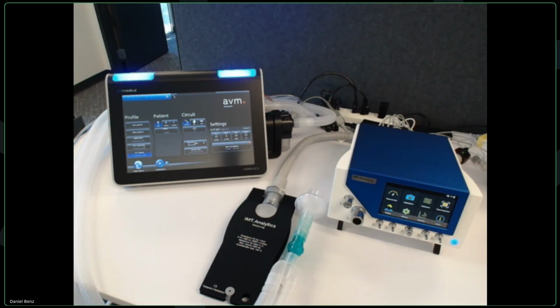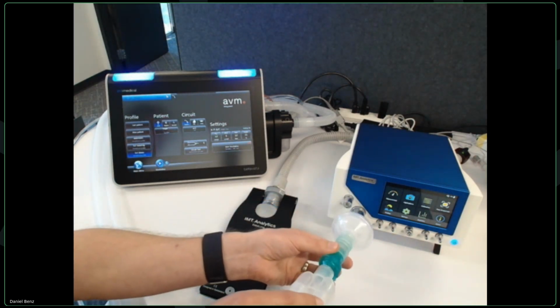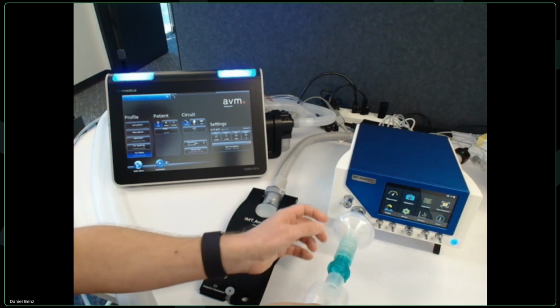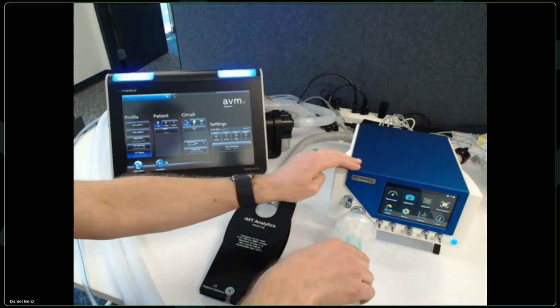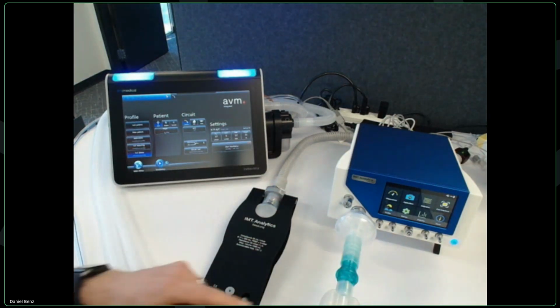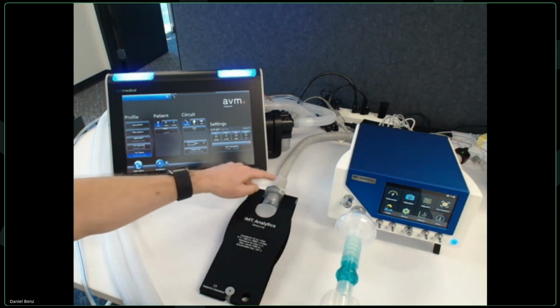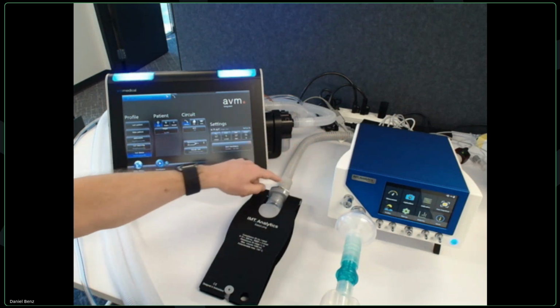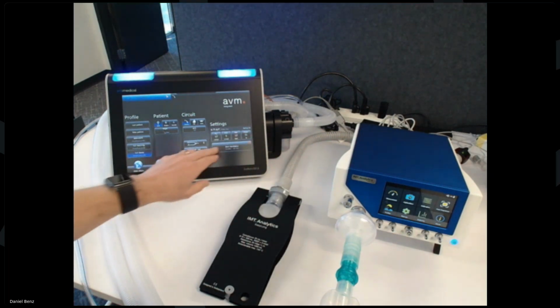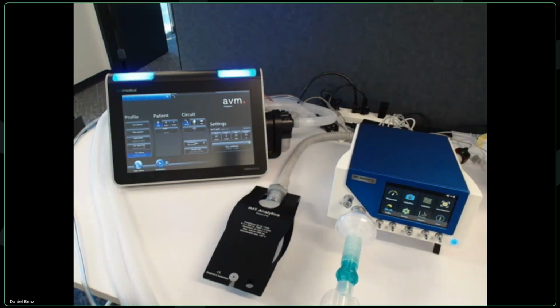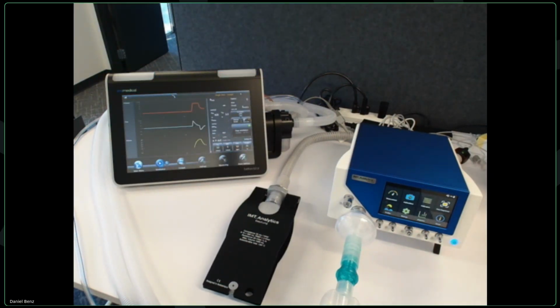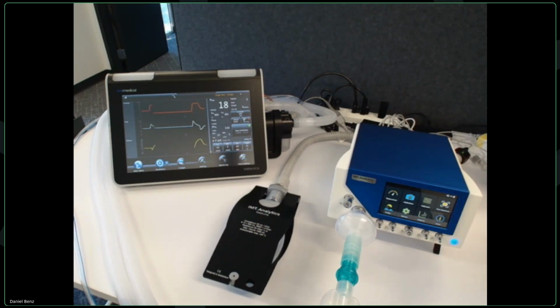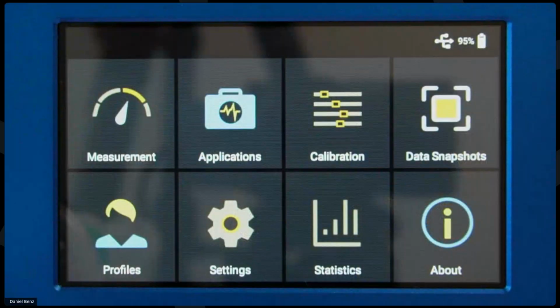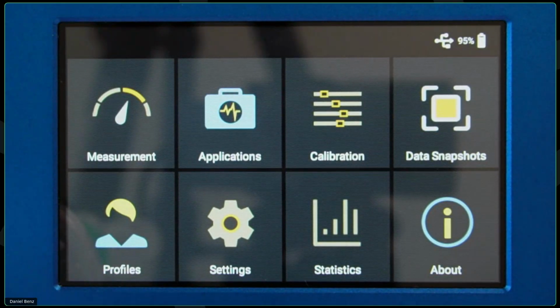And connecting my ventilator to the FlowAnalyser is quite easy because, as I mentioned earlier, everything is being measured in this main flow channel. So I just connect my circuit system of the ventilator, using this protection filter to protect the device from contamination, to the input of my main flow channel. And at the back side, I've already connected a tube to my test lung. Now I'm going to start ventilation on my ventilator, so you can see the test lung inflating. And let's go back to our user interface.